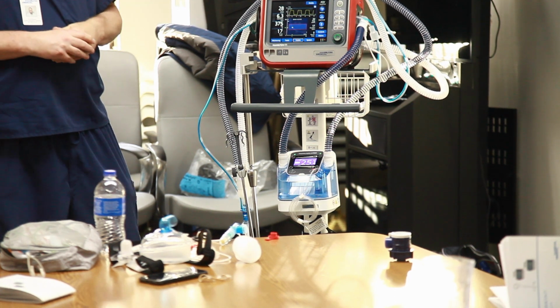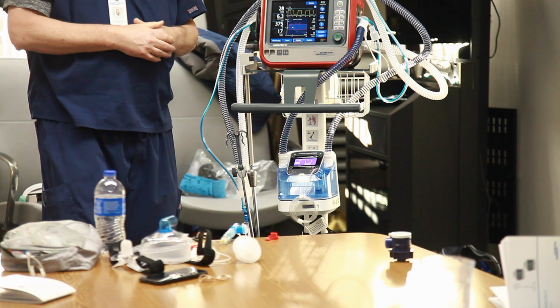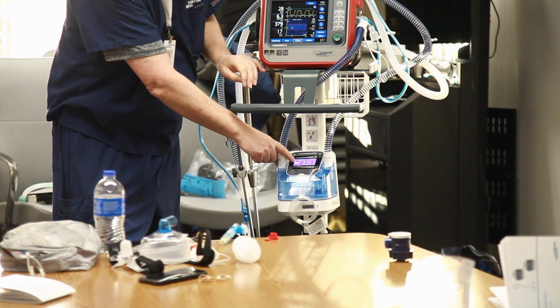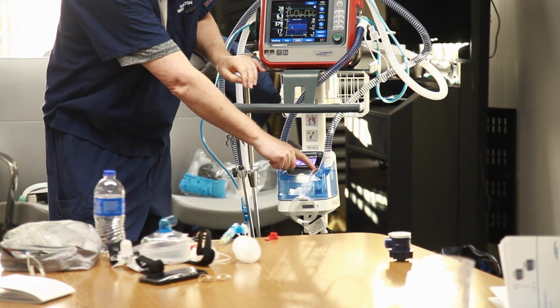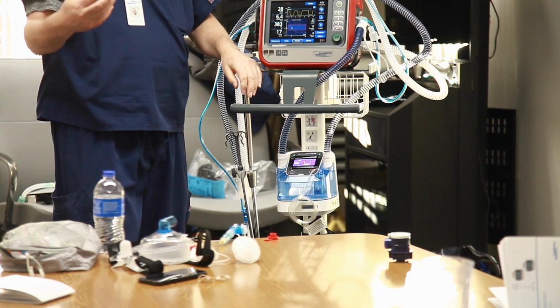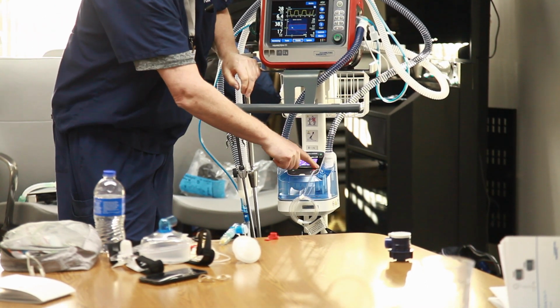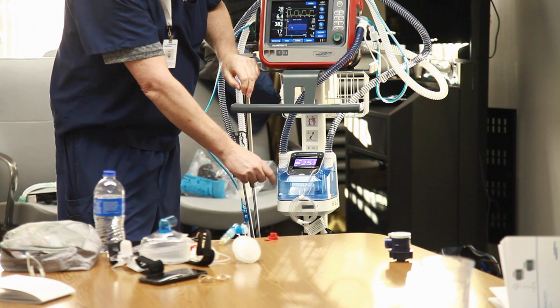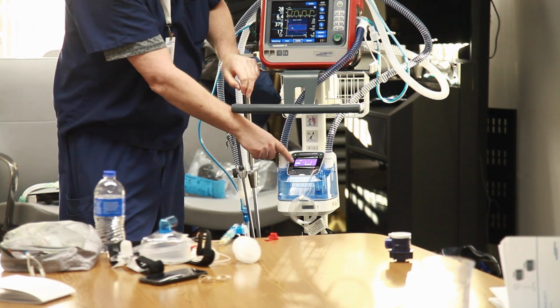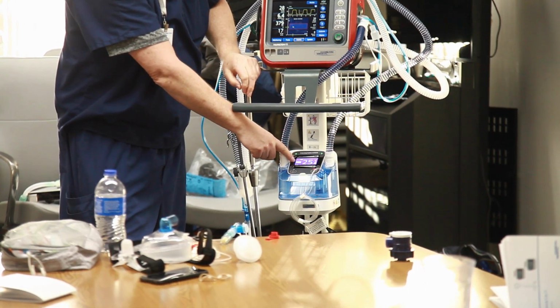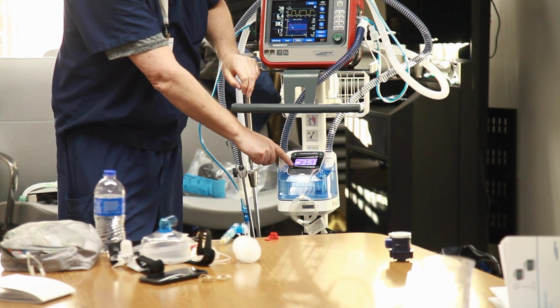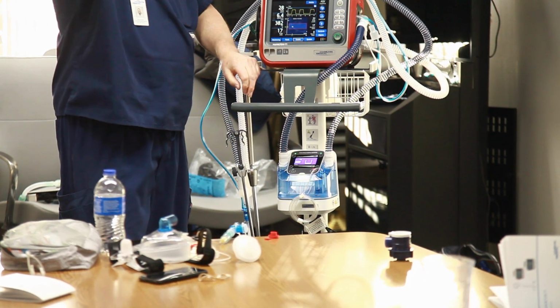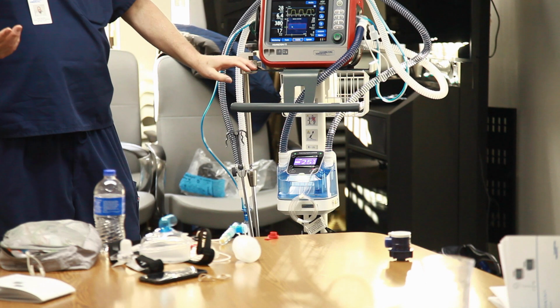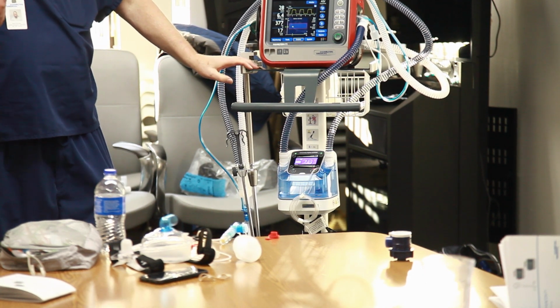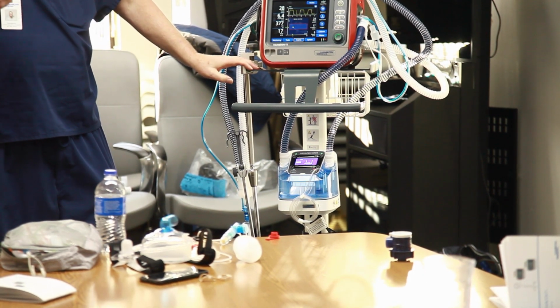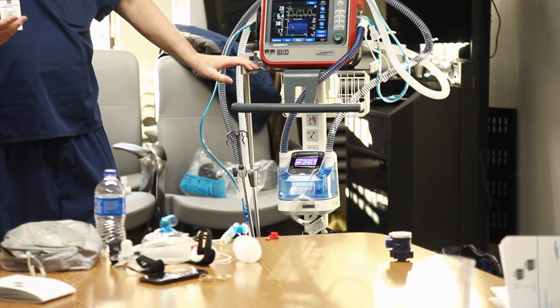Okay? If I have an intubated patient, so this is non-invasive, right? I have this little guy with a mask over here. That's how I change modes. So I push this, I have high flow. I push it again, I have invasive, INV auto. Now it's going to go up to 37 degrees with a 2 degree gradient. So it's going to be warmer to the patient. You're bypassing all that stuff, so you want to have it a little bit warmer than you do for non-invasive ventilation.